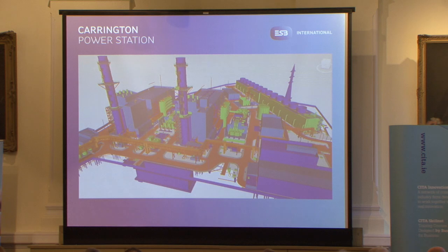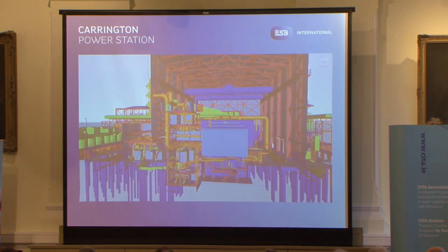This is Carrington Power Station — an 820 million pound sterling job built for ESB by EPC contractors Alstom Power and Duro Felguera. It's modelled in Aveva authoring software, exported to Navisworks. They used this very successfully: looking at the pipe rack at the front, they built it in sections — pipes were fabricated away from site, then when brought on site they scanned the next piece required to ensure millimetre accuracy. It worked for the whole job. When we came to site as site engineers, we used it for coordination of pipework, drainage, and similar within the foundation.